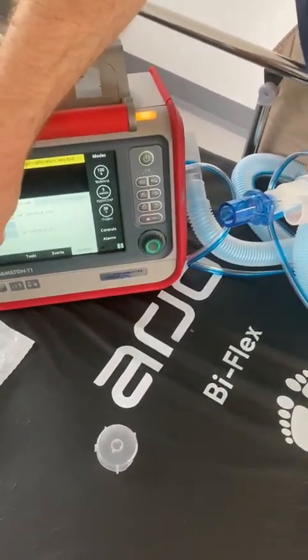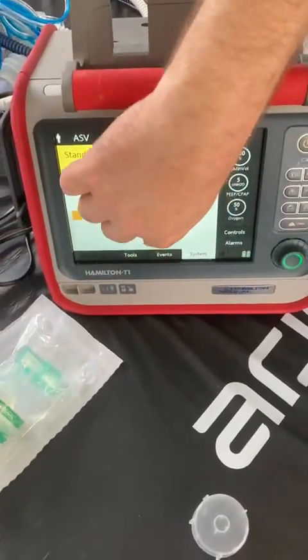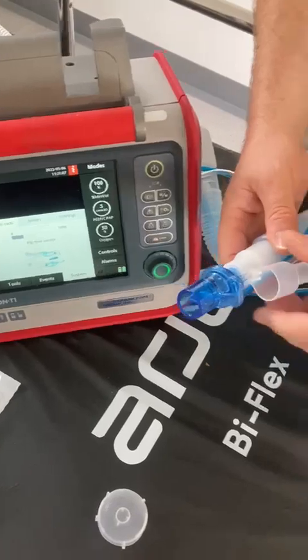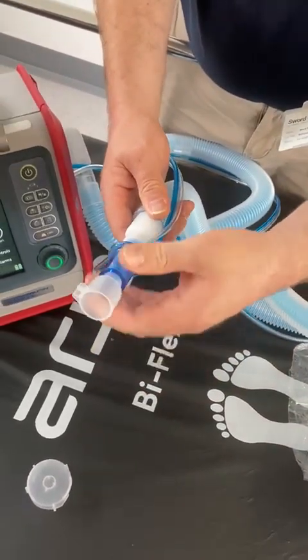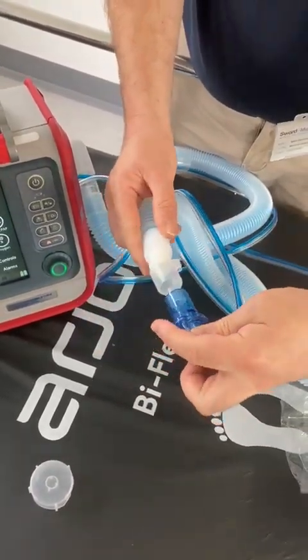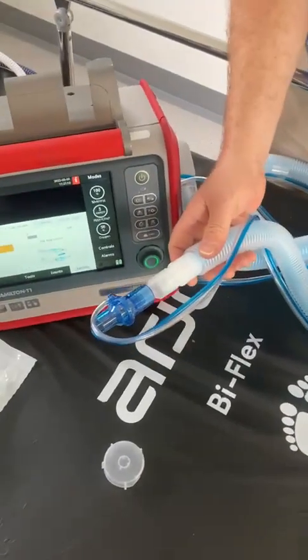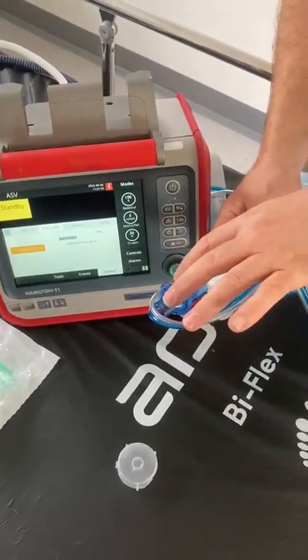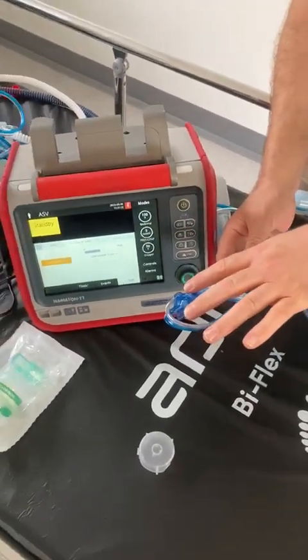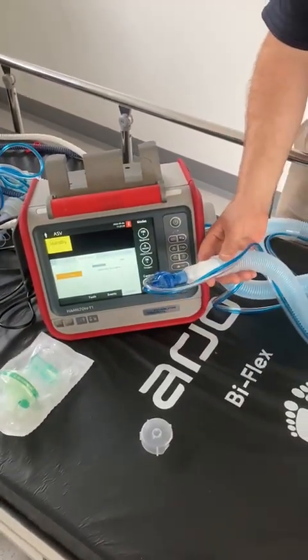So we hit flow sensor, it tells me to disconnect the patient, obviously we have, and then it prompts me to flip the flow sensor. So we plug in our adapter, unplug the flow sensor and plug it in backwards. You only get 10 seconds, it's a time limited prompt, so if you don't do that within 10 seconds, the test will fail and make you start again.